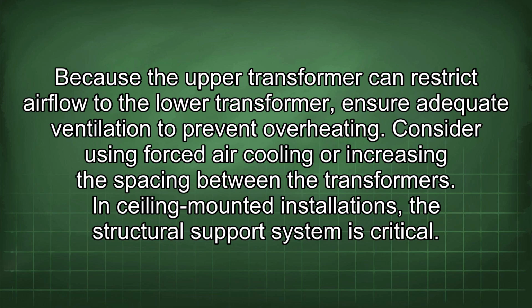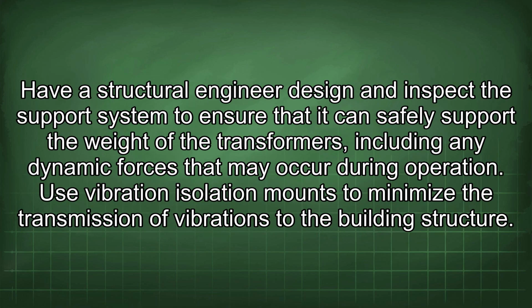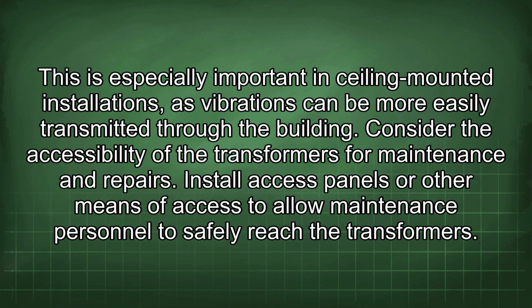In ceiling-mounted installations, the structural support system is critical. Have a structural engineer design and inspect the support system to ensure that it can safely support the weight of the transformers, including any dynamic forces that may occur during operation. Use vibration isolation mounts to minimize the transmission of vibrations to the building structure. This is especially important in ceiling-mounted installations, as vibrations can be more easily transmitted through the building.